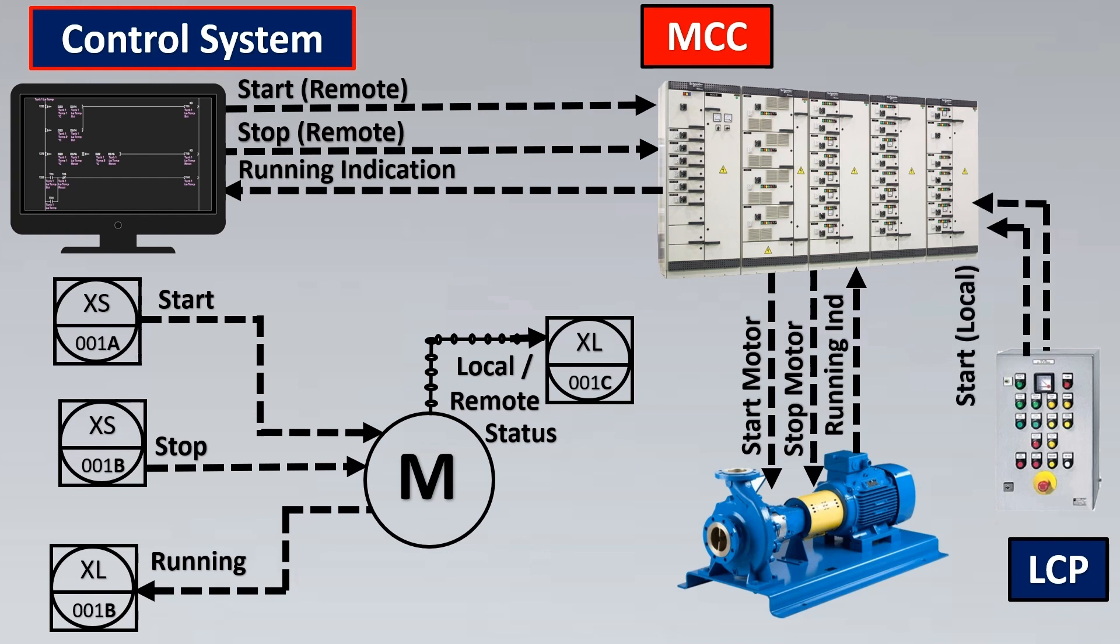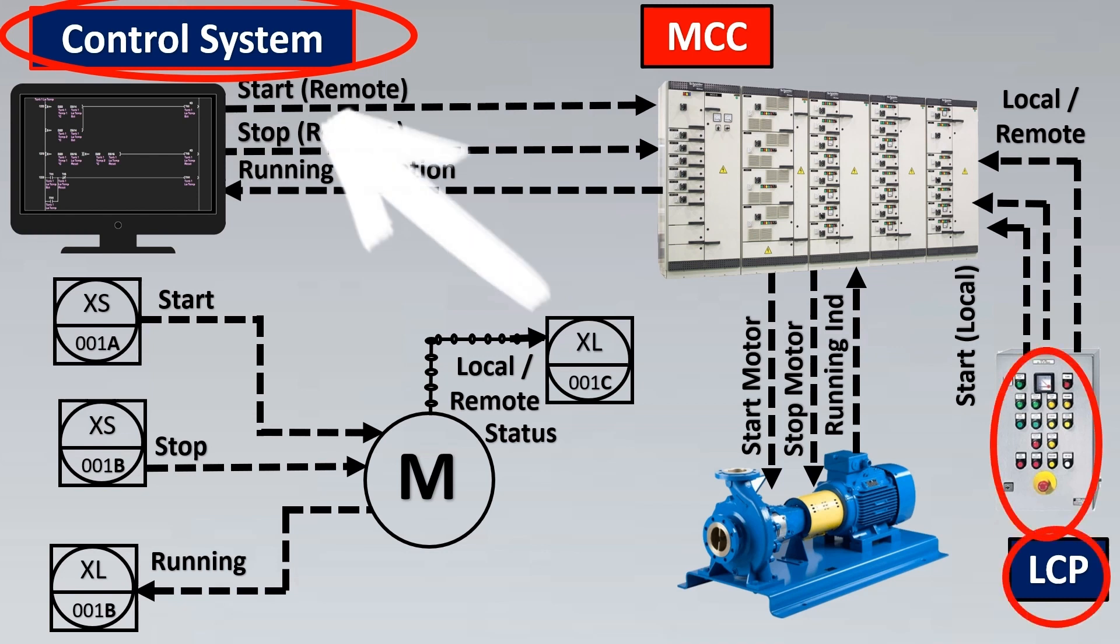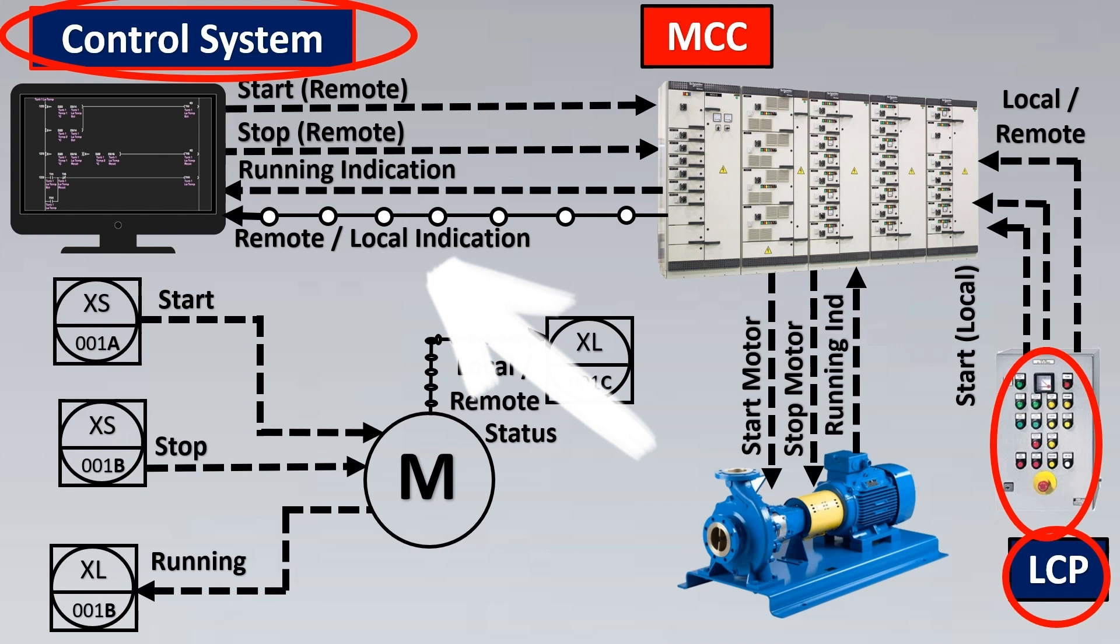This means you can start the motor, stop the motor, and have the local remote indication transferred back to your control system. Sometimes you can control the motor via control system, sometimes via LCP. How would the operator know if the motor is in operation via control system commands or the local control panel? For that we have a remote local indication. This signal sometimes is a soft signal, which helps us understand if this motor is working in remote mode via control system or local mode via local control panel.